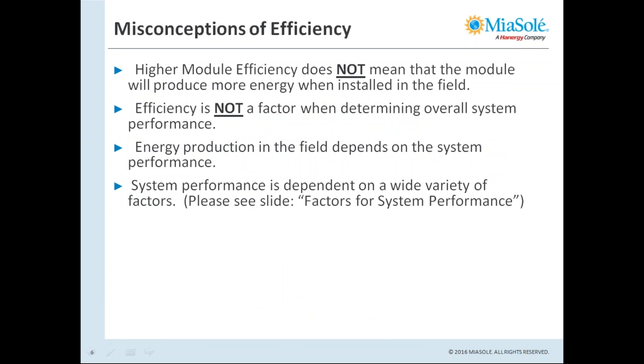It is important to remember that DC capacity must be the same to compare efficiency fairly. There are two common misconceptions I'd like to caution you about. Number one: a higher efficiency module does not mean the module will produce more energy when installed in the field. Number two: efficiency is not a factor when determining overall system performance. Efficiency is all about power within a given area — it does not guarantee or equate to expected field performance.